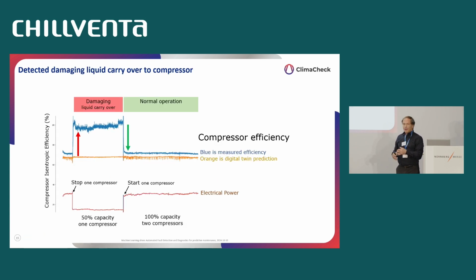This is showing, some of you might have come across that there are problems with some compressors when you have tandem connection. So if one of them leaks backwards, the other one will fail. Because there's refrigerant going through the standstill compressor over to the operating compressor, which brings too much oil into that compressor, and then it pours out the oil, and the oil comes back saturated with liquid refrigerants.